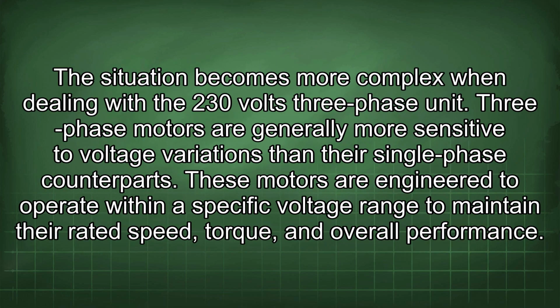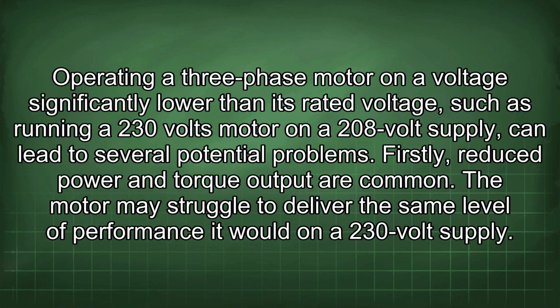The situation becomes more complex when dealing with the 230 volts three-phase unit. Three-phase motors are generally more sensitive to voltage variations than their single-phase counterparts. These motors are engineered to operate within a specific voltage range to maintain their rated speed, torque, and overall performance. Operating a three-phase motor on a voltage significantly lower than its rated voltage, such as running a 230 volts motor on a 208 volt supply, can lead to several potential problems.